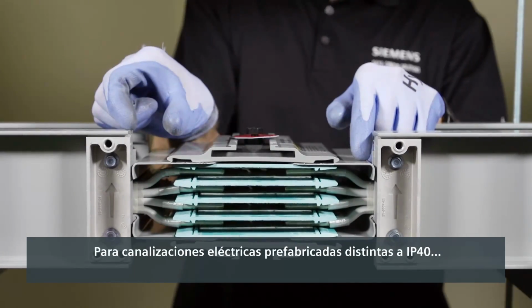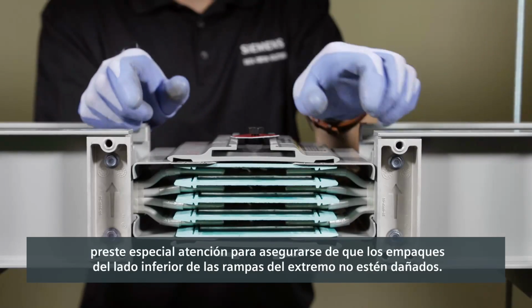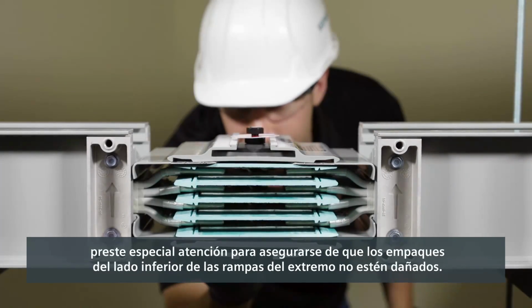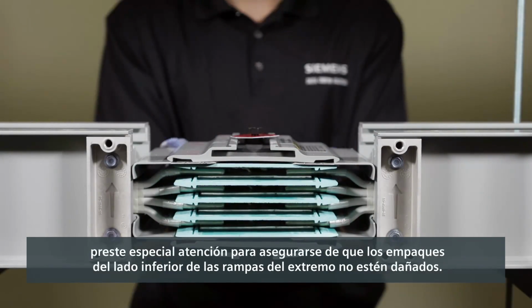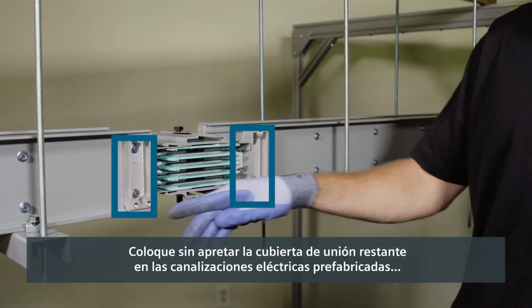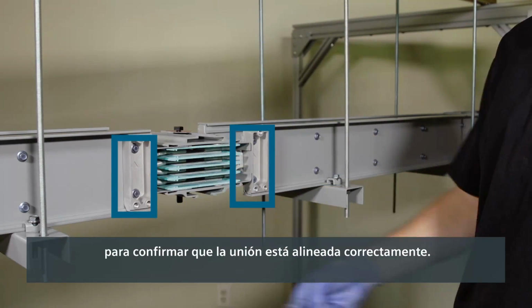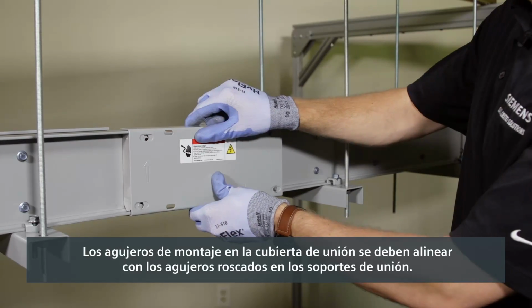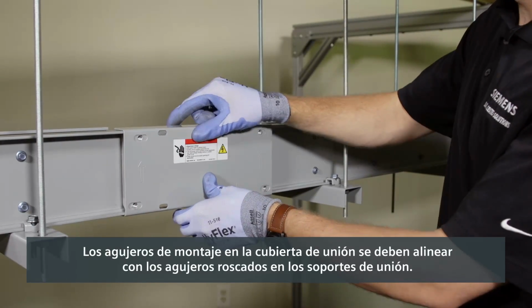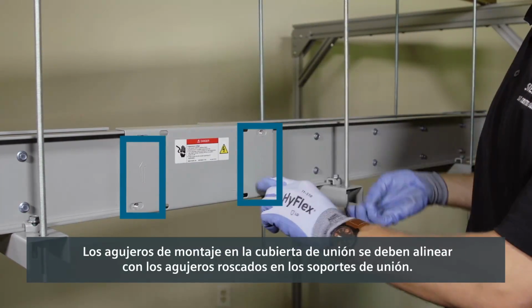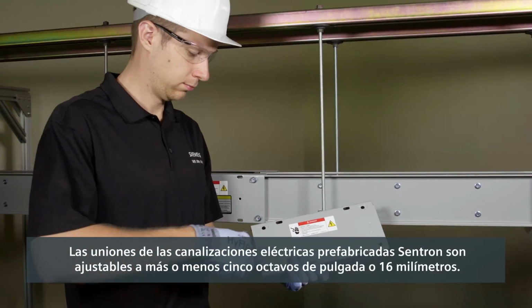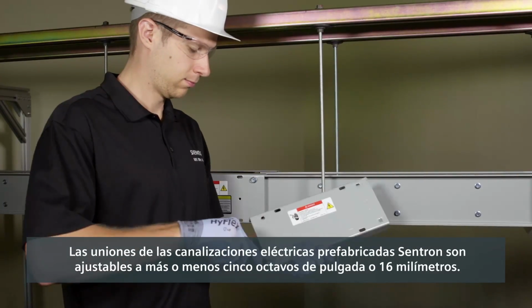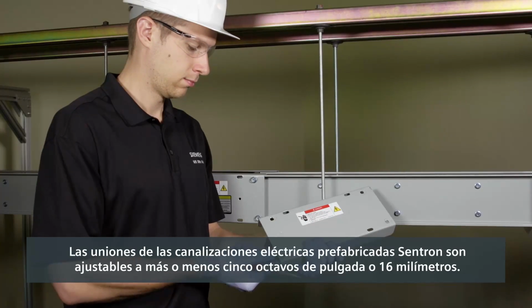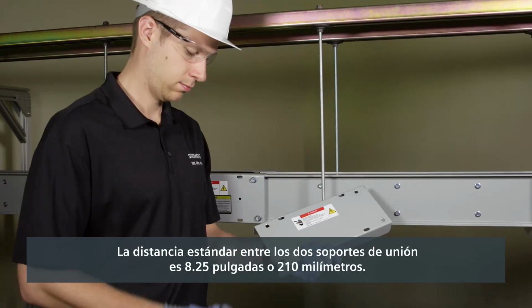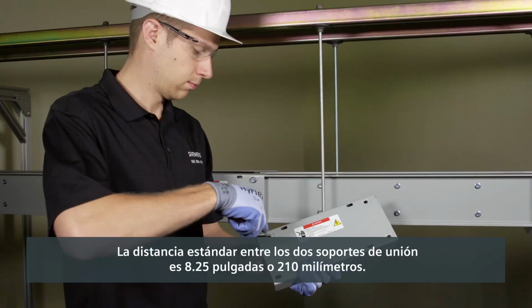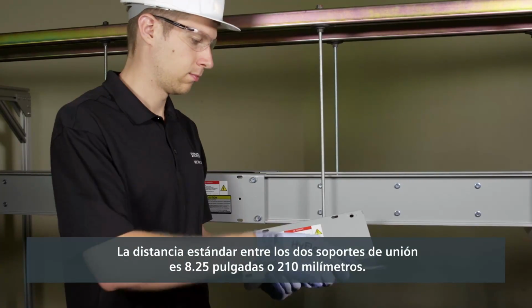For busway other than the IP40, pay special attention to be sure the gaskets on the underside of the end ramps are not damaged. Loosely fasten the remaining joint cover to the busway to confirm the joint is aligned properly. The mounting holes in the joint cover should line up with the threaded holes in the joint supports. Sentron busway joints are adjustable to plus or minus 5/8 of an inch, or 16 millimeters. The standard distance between the two joint supports is 8.25 inches, or 210 millimeters.